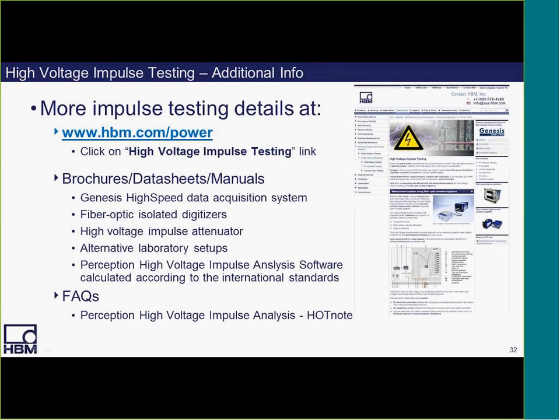So, to sum up, where you can obtain additional information on impulse testing details, you can go to hbm.com/power, and then you'll see a link called High Voltage Impulse Testing. Just click on that link, and you'll be able to obtain more information, including brochures, data sheets, and manuals for the hardware, the Genesis high-speed data acquisition system, the fiber optic isolated digitizers, the high voltage impulse attenuator, alternative laboratory setups, in addition to the one we just showed you previously, plus the perception high voltage impulse analysis software, calculating according to the international standards. There's also an FAQ section with some of the more common questions on the impulse analysis software.